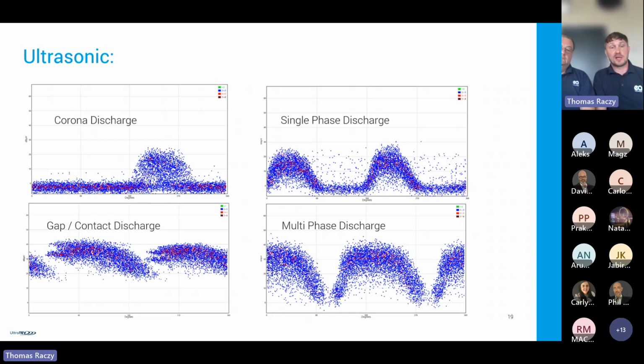Again, it's possible to detect those discharges with ultrasonic sensors as well, because there will typically be some earth path through which the signal will travel to the pickup, and they again tend to be very similar magnitude across the power cycle for all the discharges. Sometimes there's a bit of this trail off happening.